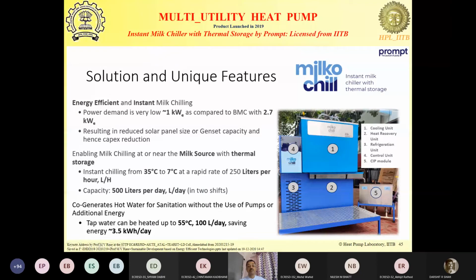So compared to the conventional bulk milk coolers, which consume for 500 liter per day capacity, the peak power is around 2.7 kilowatt. Our peak power is about 1 kilowatt. Okay. The energy saving is also there because we are generating potable, means sanitary water heated up to 55 degrees centigrade. So that gives additional saving of 3.5 kilowatt hours per day. Okay. And conventional bulk milk cooler cools the milk within 3 hours. Ours is able to cool it in less than 1 hour if the entire 250 liter is poured together. But if you take the time from when the milk is poured to the time it takes for the milk to travel through the heat exchanger, it's only 30 seconds, less than 30 seconds actually.